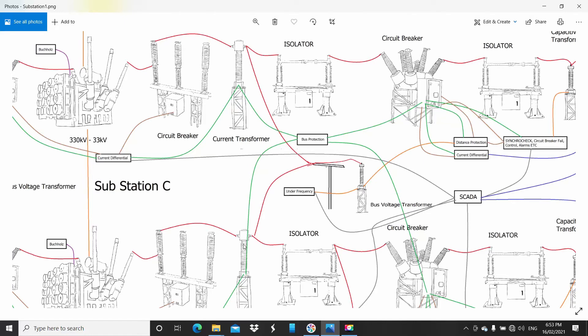The whole idea is if a current develops in that circuit, then it would send a trip signal and open every single breaker on that bus. That would be everything in and everything out. That's how bus protection works. Again, I'm going to have another video on high impedance bus protection to explain it a bit more in detail because that's quite complicated, especially with the math.